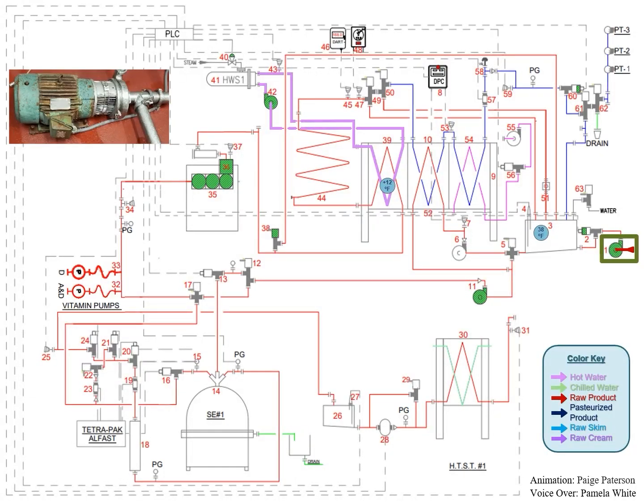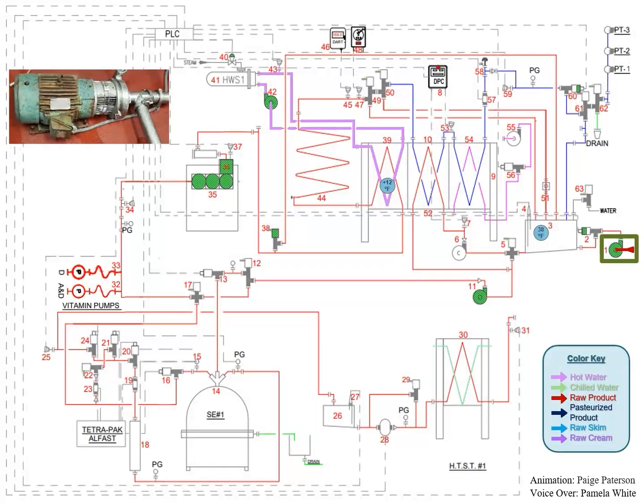This will cause the balanced tank milk inlet throttling valve to close most of the way when the raw storage tank is full and open most of the way when the raw storage tank is near empty.